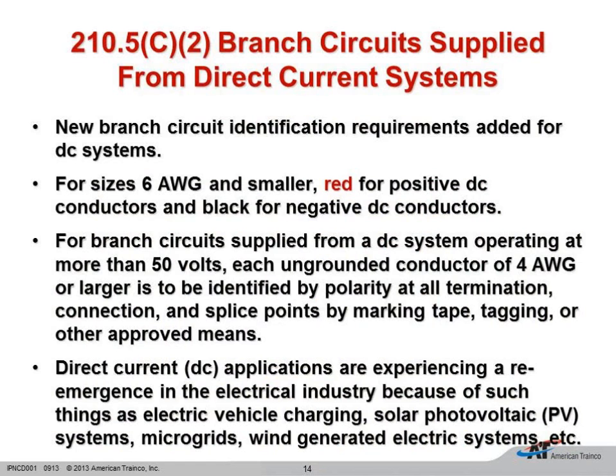210.5 C2, as I said earlier when I introduced the whole webinar, DC systems have been affected a lot in this edition of the National Electrical Code. So they have finally given us a color code, the same color code we've used for most of our life. Red is going to be for the positive conductor, and black is going to be for the negative conductors, and you can see that's for size 6 and smaller.